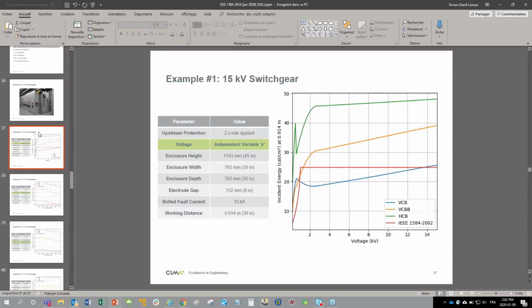Right. Okay. This one from Richard. Considering an electrical distribution system that's not barriered between sections, when calculating the incident energy at the line side of the main, do you use the main cubicle dimensions or the dimensions of the entire lineup? Well, normally if there's a separate cell for the main breaker, and then there's an enclosure for the feeder breakers, you need to put a bus upstream of your main breaker, and then the energy on that one would exclude the main breaker in its arc flash calculations. So you'd have a label on the main breaker, and then your main breaker can be considered for the arc flash on the feeder breakers. And if they're all in a single large enclosure, then the large enclosure would be the only size that you put inside EasyPower.